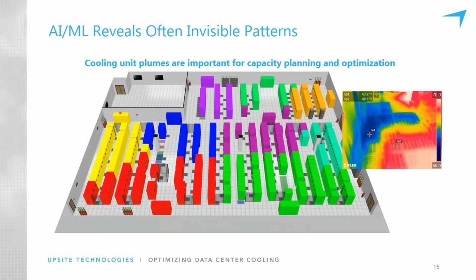So this becomes really useful in identifying things like where is there redundant capacity and how do we make adjustments that actually make a good impact in the room. Because quite often data center operators, with good intentions, are making adjustments to set points and controls, but they're doing it to the wrong cooling unit. You're adjusting the wrong parameter because you don't know what's actually happening in the computer room. So great insights can be realized, and the visuals make it very, very clear.